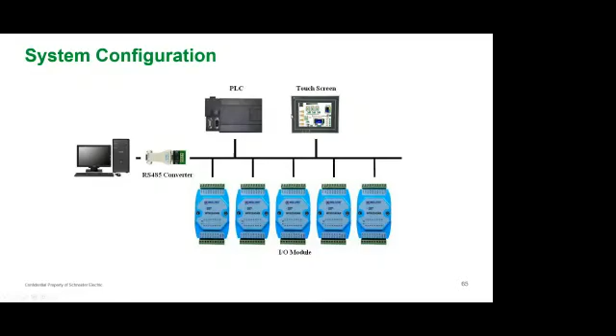I wanted to show you a quick glance at industrial network protocols. Protocols are communication mediums between devices in the field. Your control room connects through Ethernet to a PLC, while HMIs and field devices like drives, gateways, meters, and sensors may communicate through different mediums like RS-232, RS-485, etc. These get converted through gateway devices and then connected to the PLC, because most field devices aren't Ethernet compatible - existing devices that are about 5 years old are typically RS-232 or RS-485 based. They need a converter to transform the signal before it's transferred to the PLC, and from there you can view, monitor, and control the signal through the SCADA system or HMI.